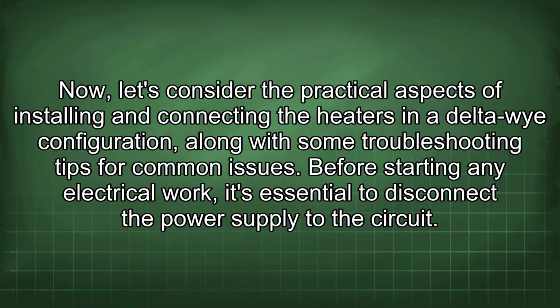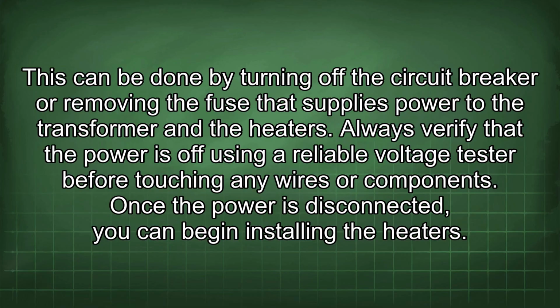Before starting any electrical work, it's essential to disconnect the power supply to the circuit. This can be done by turning off the circuit breaker or removing the fuse that supplies power to the transformer and the heaters. Always verify that the power is off using a reliable voltage tester before touching any wires or components. Once the power is disconnected, you can begin installing the heaters.